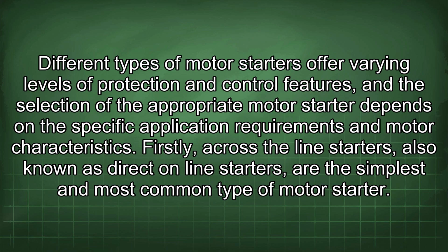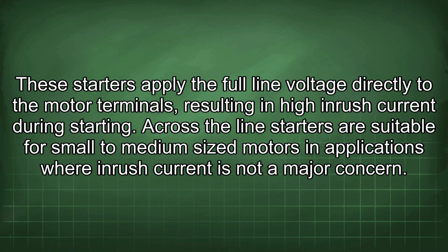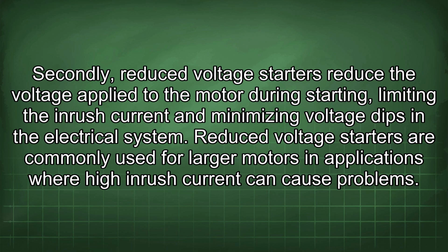Firstly, across-the-line starters, also known as direct-on-line starters, are the simplest and most common type of motor starter. These starters apply the full line voltage directly to the motor terminals, resulting in high inrush current during starting. Across-the-line starters are suitable for small to medium-sized motors in applications where inrush current is not a major concern. Secondly, reduced voltage starters reduce the voltage applied to the motor during starting, limiting the inrush current and minimizing voltage dips in the electrical system. Reduced voltage starters are commonly used for larger motors in applications where high inrush current can cause problems.